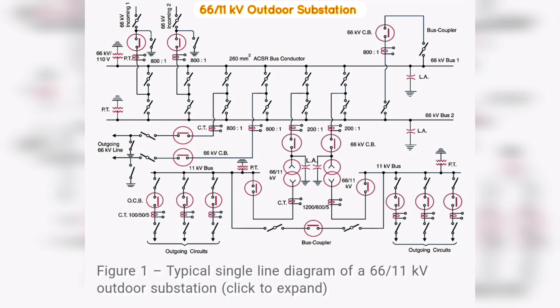If need arises, both transformers can be called upon to share the substation load. The 11 kV outgoing lines feed to the distribution substations located near consumers' localities. Both incoming and outgoing lines are connected through circuit breakers having isolators on their either end.